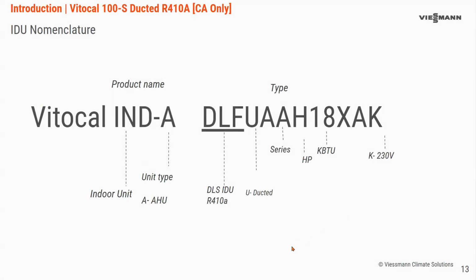And onto the indoor units, IND for indoor unit. These are all going to be IND-As because they're air handlers and A coils. DLF for the indoor unit, U for ducted, and then really your capacity there. So this is a ducted 18K air handler for the ducted units.